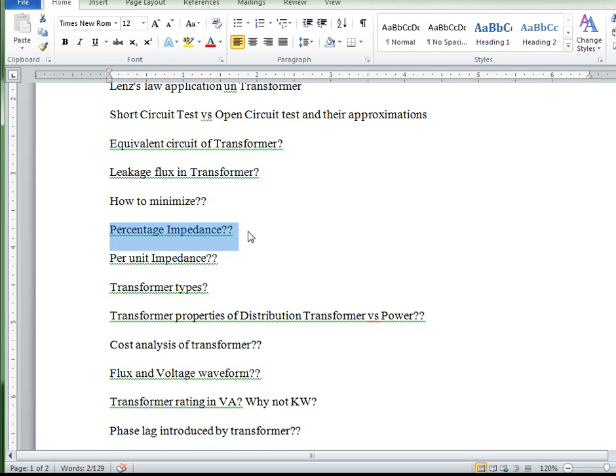Percentage Z should not be less than or more than 4%, otherwise there will be circulating currents flowing inside each branch or transformer. Whenever WAPDA asks you to deliver a transformer, their normal value is 3.98 to 4.02%. So whenever you are designing a transformer, at the end of your calculation, if your percentage Z comes out to 4.1 or 4.2%, the whole design is rejected. You go back to the start, take some other value and design it again. The first parameter of a successful design is percentage Z, which should come to 4% for a distribution transformer. For a power transformer, this same value of percentage Z is 8 or 9%.